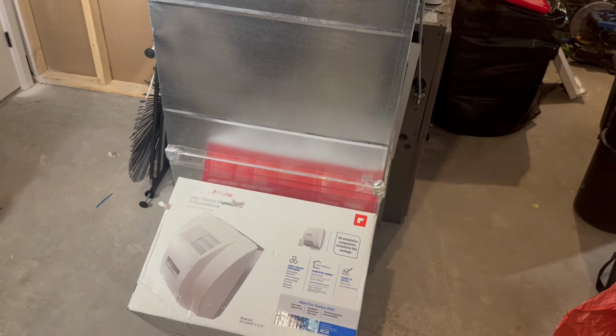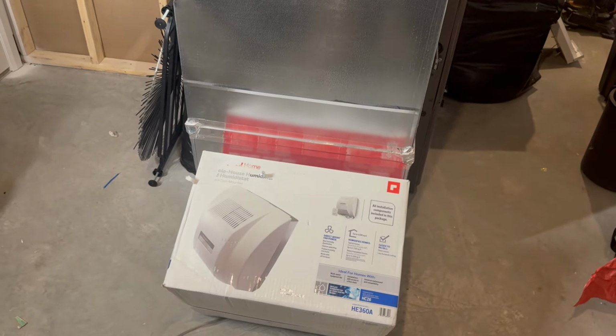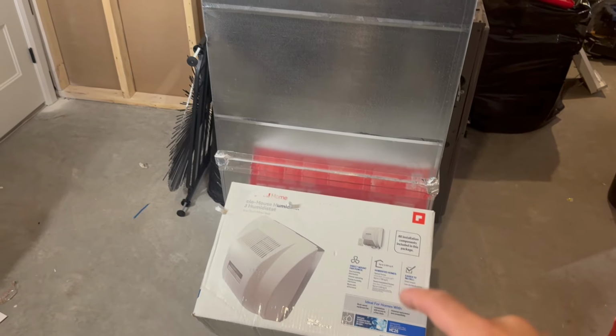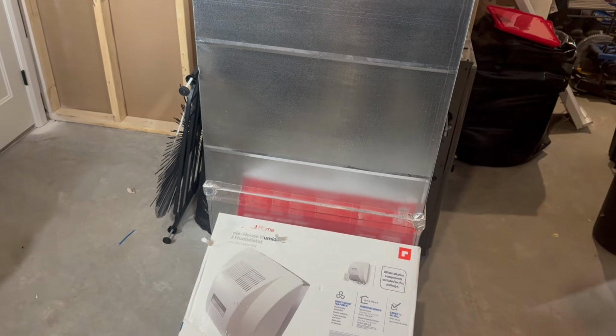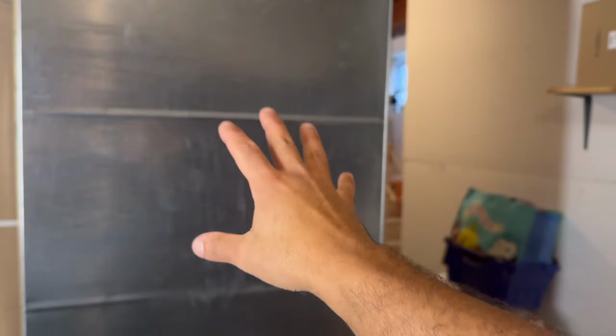Now, if you have an Aprilaire unit and it's a bypass duct, in that case, you'll want to mount it on the return side and then have your bypass duct run to the supply side. Thankfully, I have room on the supply side of my furnace. But if I didn't, in that case, I would have no choice but to put it on the return side.